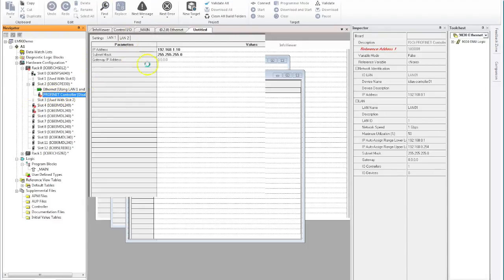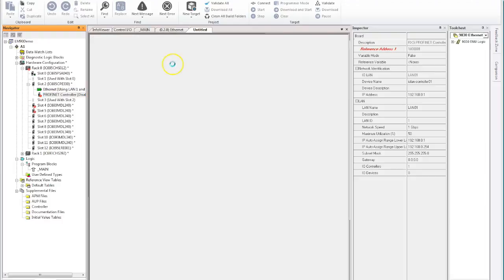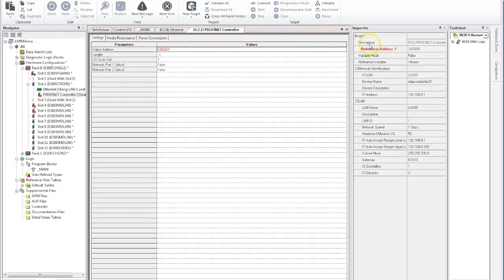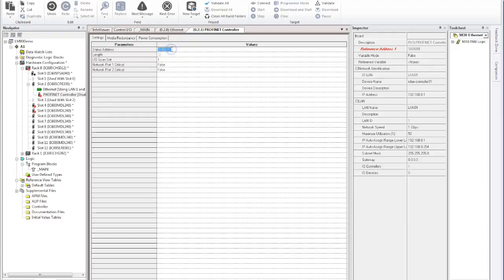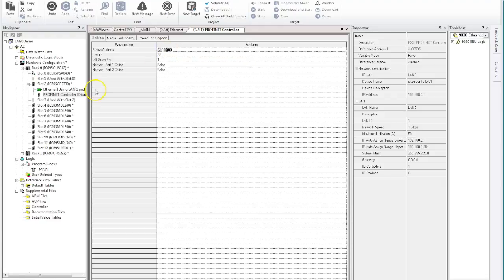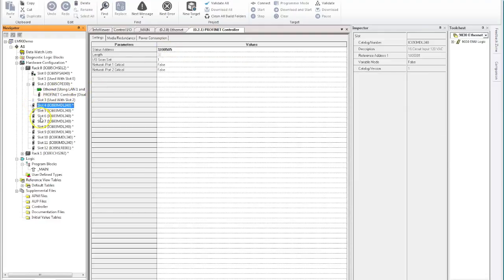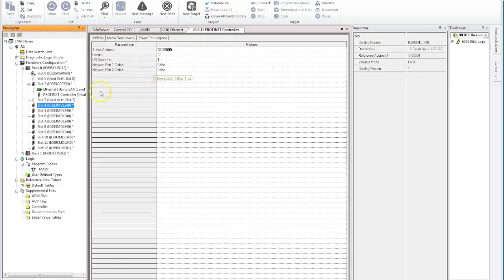The reason for that is the PROFINET defaults memory space is %i1. We don't particularly use this when we get into our programming, but it's just the default memory allocation in the background. In this particular case, because we've got existing IO, we'll set this back up in the 500 region. It grabs the next available, so 505, and you'll now see that all the other errors have now cleared on those slots. That's because the IO ports start at %i1, and that's always been the case even on the old 90-30s.